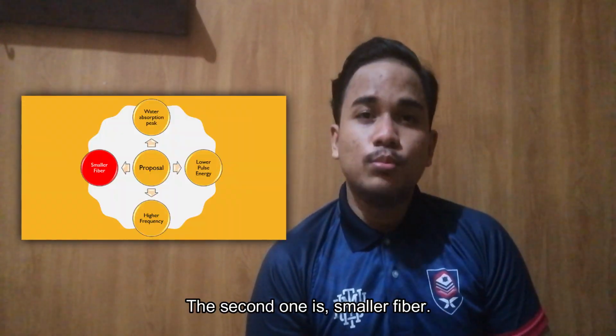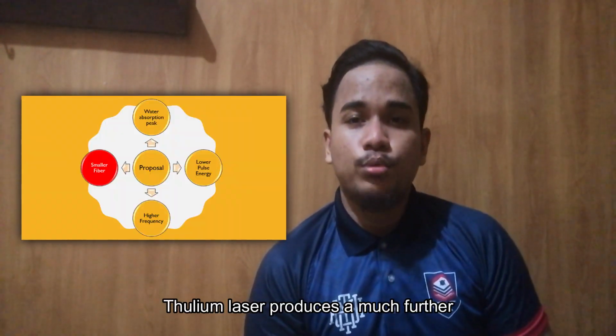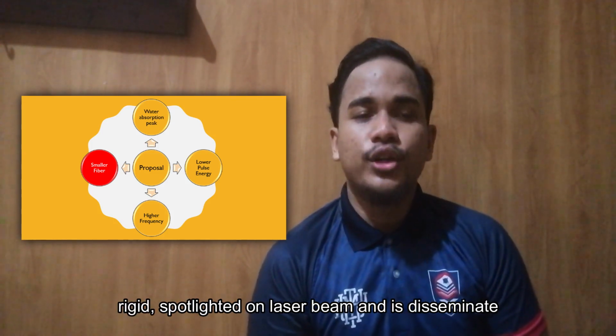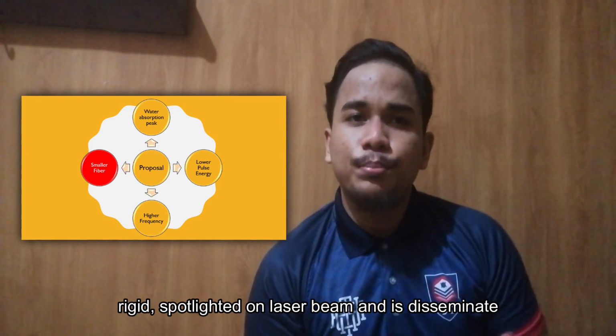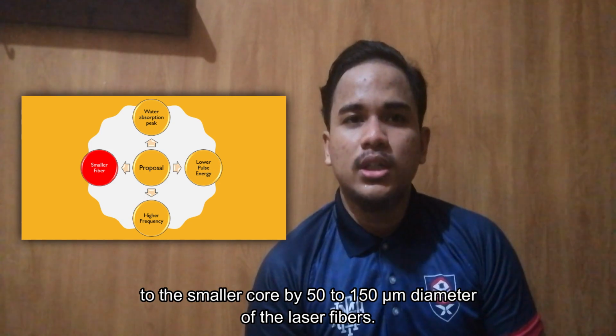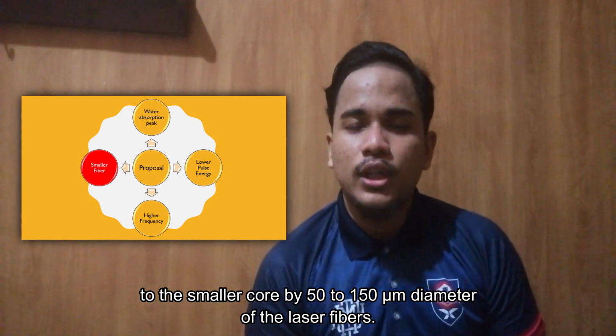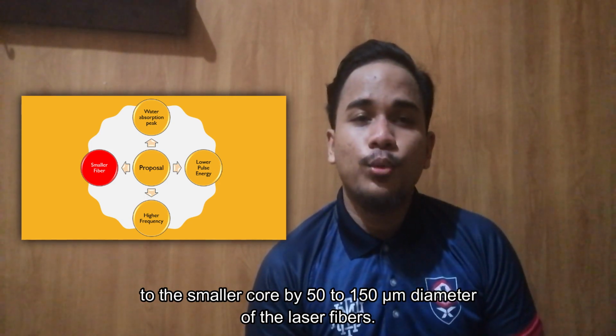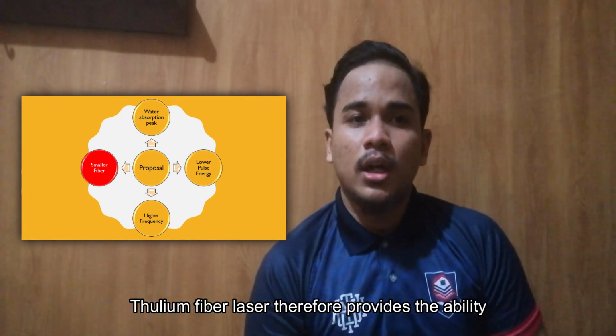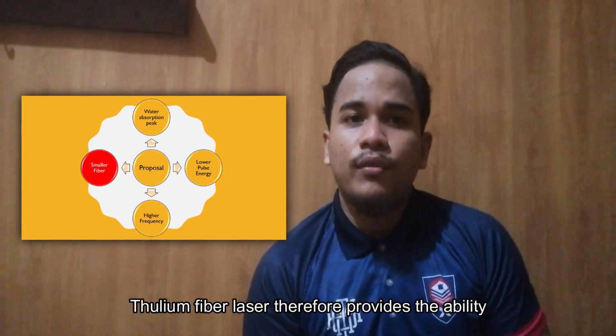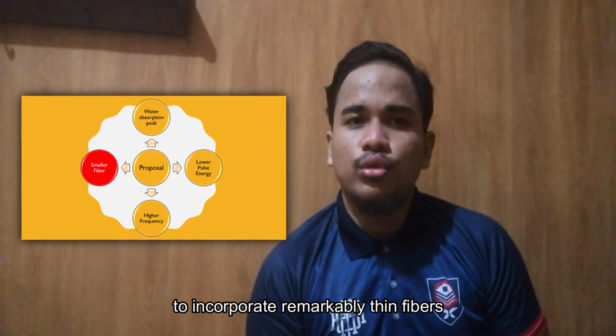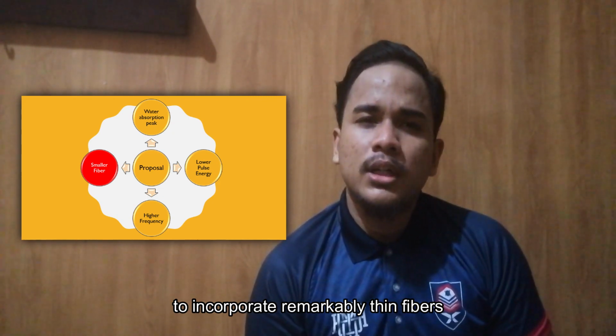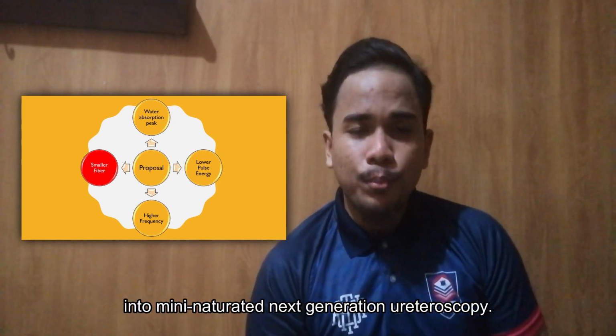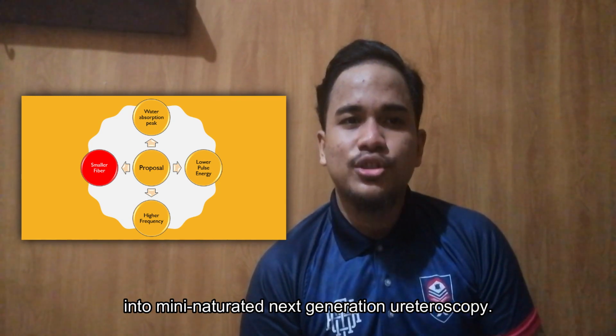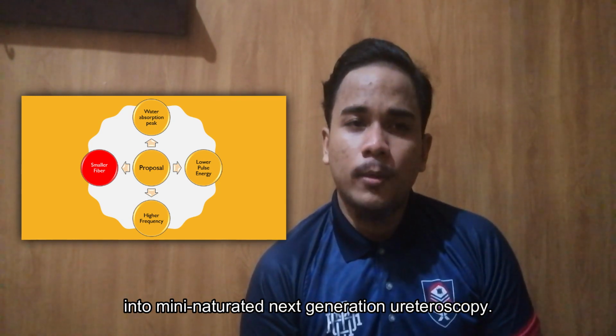The second one is smaller fiber. Thulium laser produces a much tighter spotlight on the laser beam and is disseminated to a smaller core, by 50 to 150 micrometer diameter laser fibers. Thulium fiber laser therefore provides the ability to incorporate remarkably thin fiber into miniaturized next generation ureteroscopy.